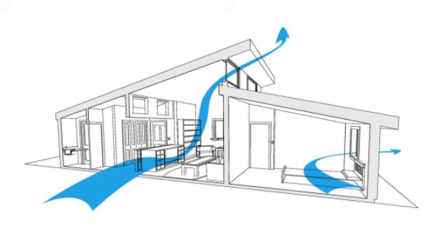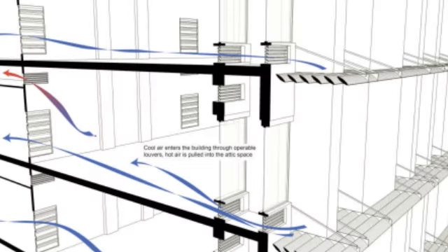In many instances, ventilation for indoor air quality is simultaneously beneficial for the control of thermal comfort. At these times, it can be useful to increase the rate of ventilation beyond the minimum required for indoor air quality. Examples include airside economizer strategies and ventilation pre-cooling. In other instances, ventilation for indoor air quality contributes to the need for, and energy used by, mechanical heating and cooling equipment. In hot and humid climates, dehumidification of ventilation air can be a particularly energy-intensive process.